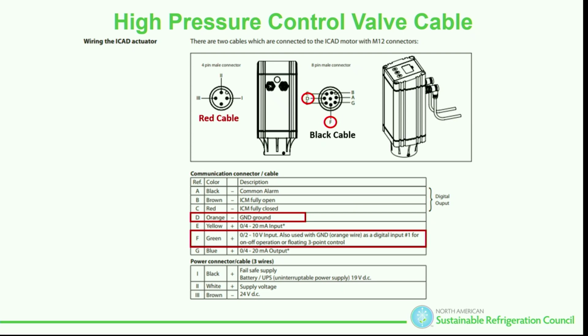The one I was talking about, we had 0 to 10 volt there at the cable. So what was bad? The actuator was bad. The motor wasn't driving because we weren't getting the signal. Yes? I mean, it was getting the signal, it just wasn't processing the signal. Everybody see what we did? So we've got to approach these things this way. And this is a kind of a CO2 thing, because I'm not going to have this unless I'm an ammonia guy. This valve's on ammonia big time. It's an expansion valve for the ammonia world.